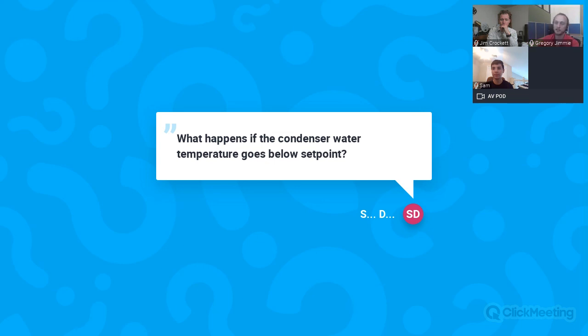So like I had briefly mentioned, a York chiller, let's say it's an 8-degree differential. That assumes the worst case scenario. Think about it in the sense that you're able to achieve the coldest condensing water temperatures under usually the lowest outside air temperatures, right? And that also corresponds to your warmest chilled water because you've got the least amount of cooling demand in your system. So that's really where you're going to hit the point of, okay, I need to maintain at least this differential between the two. So if we run with the 8-degree example, if you're able to reset up to 50 degrees on the chilled water side, you really shouldn't go below 58 on your condensing water side.